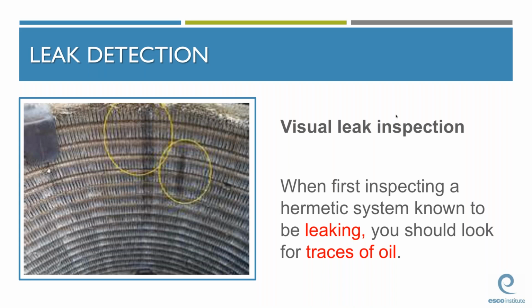Two of the most valuable leak detection methods are your eyes and your ears, and make sure you let your students know about that. When inspecting an operating system that's known to be leaking, they definitely want to look for traces of oil. Make certain that you emphasize to your students that oil travels through the system along with the refrigerant. So when the refrigerant leaks from a system, so does some oil. Although the refrigerant vaporizes, the oil doesn't. It remains behind and can often be spotted. In addition, listening for leaks will help you locate large system leaks.